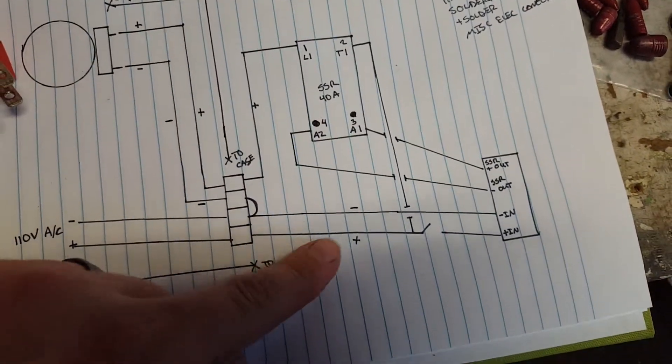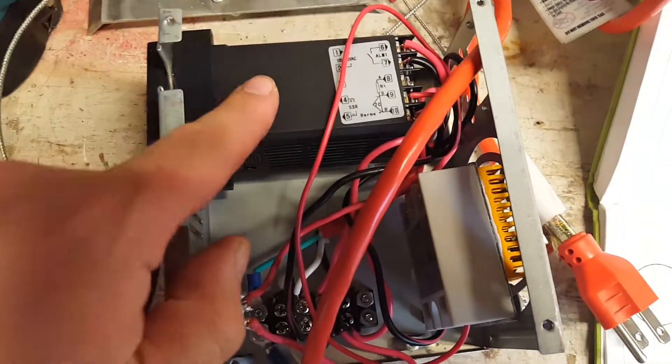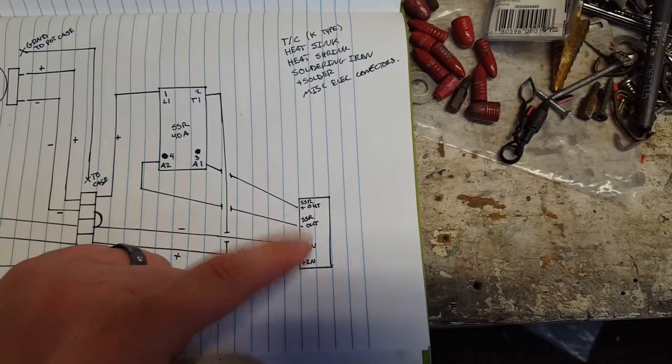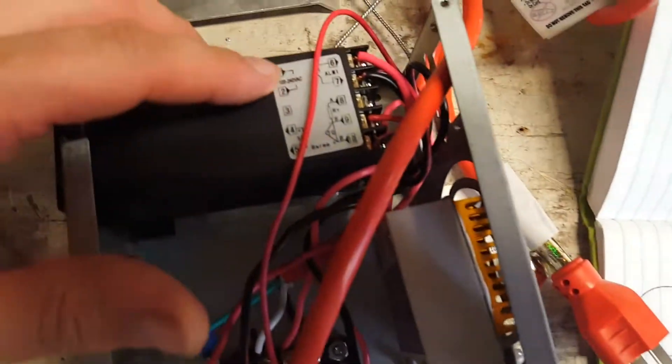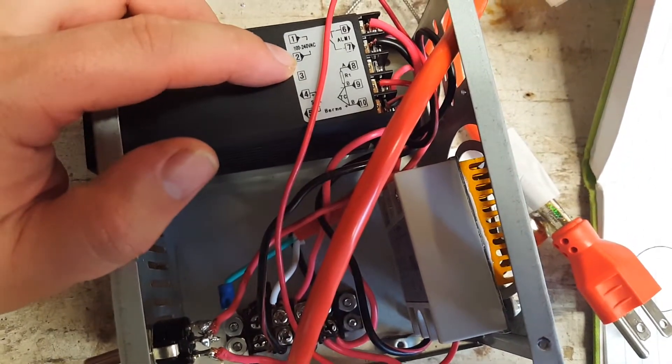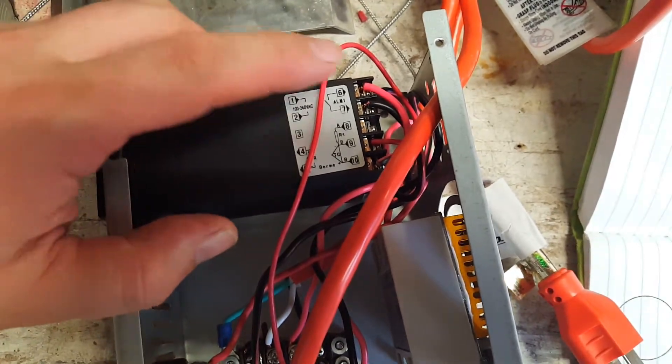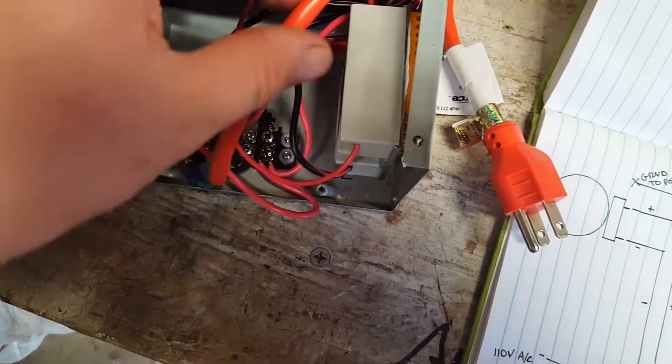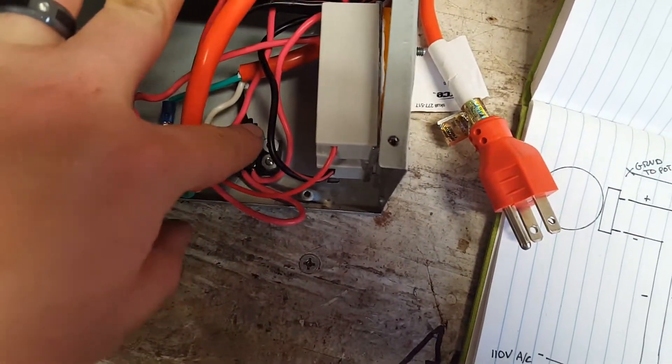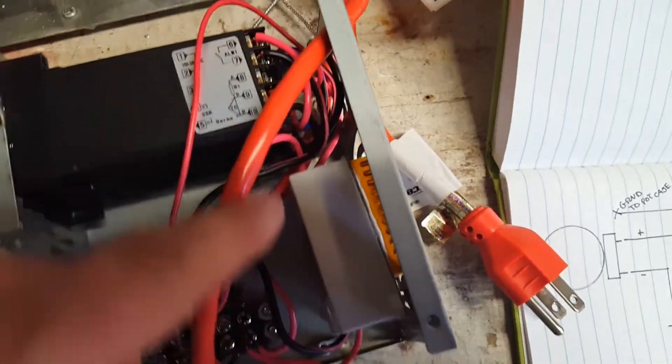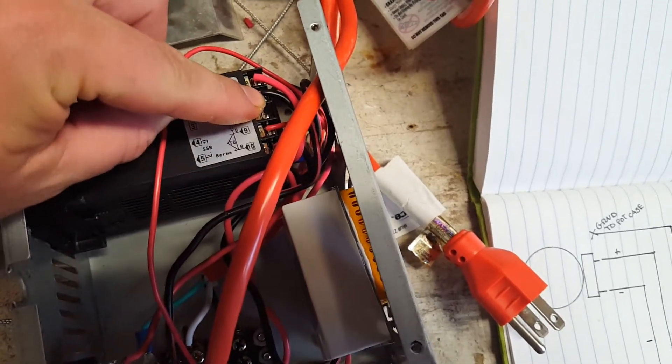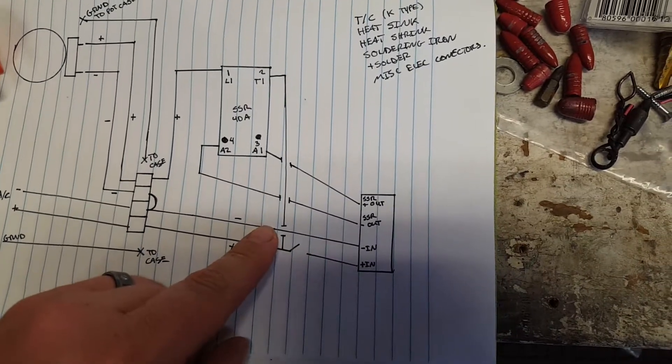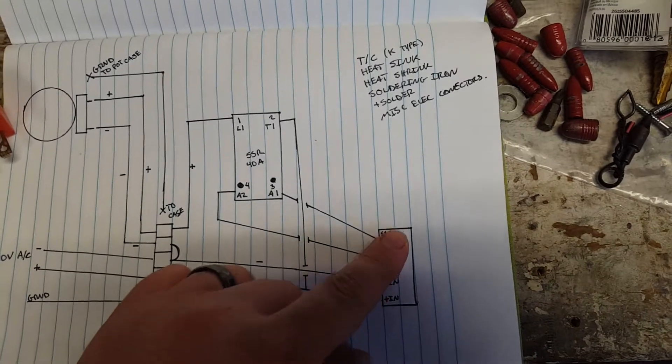Positive comes to switch. This is the PID controller itself, which is right here. I did not put the positions on the PID controller because every PID controller is different. For this one, terminals one and two were positive and negative, and it doesn't even list what is positive and what is negative. Position one is positive, position two is negative. Once it leaves this cord, I don't have black and white wires, so I used red and black. So red is positive and black is negative.